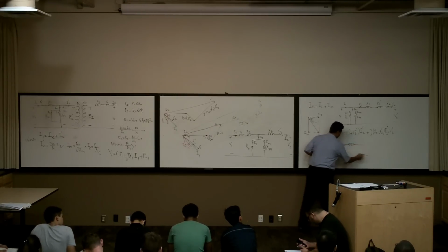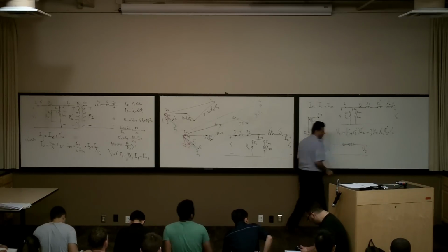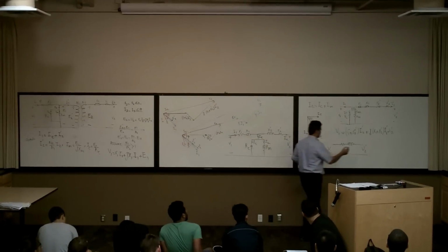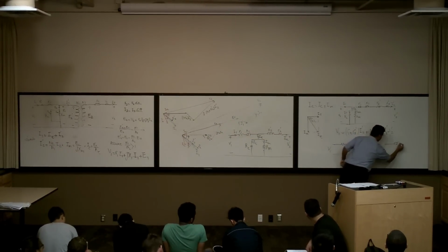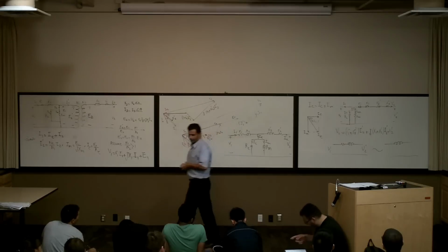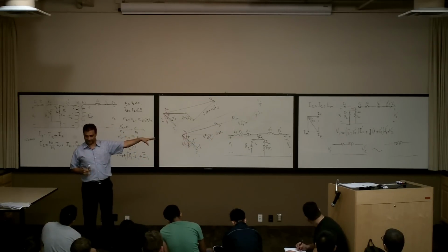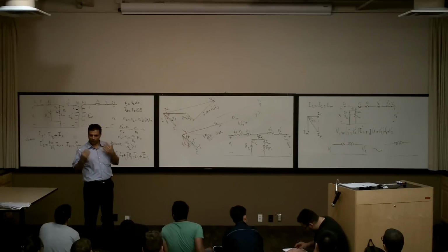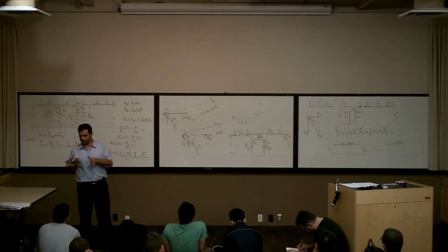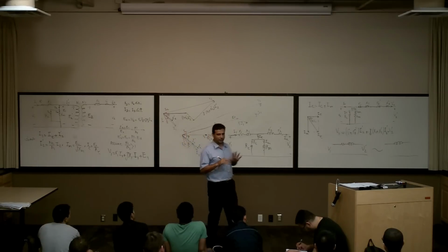R, X. V1, V'2. Right? If we get rid of the R, we use this. This is for the next chapter. Get rid of the R. Okay? R is not that much. Forget it. Just X. They model the transformer only with X. So don't get confused about how the transformer can be modeled with only X. This is an approximate model, but it's pretty accurate for what we need for power systems, more than 98% accurate.